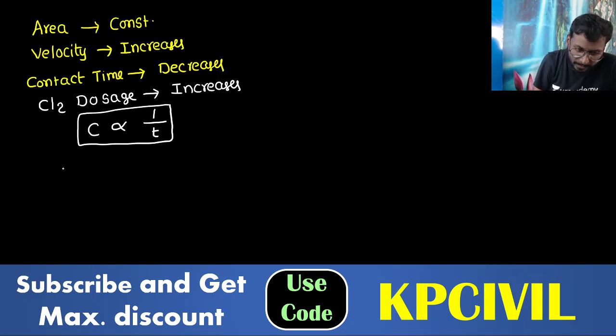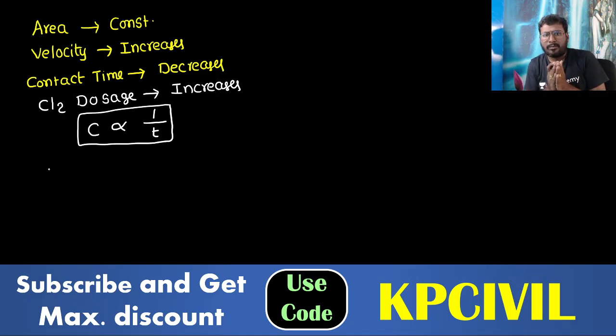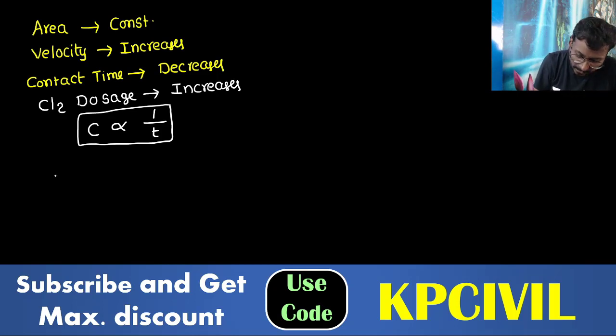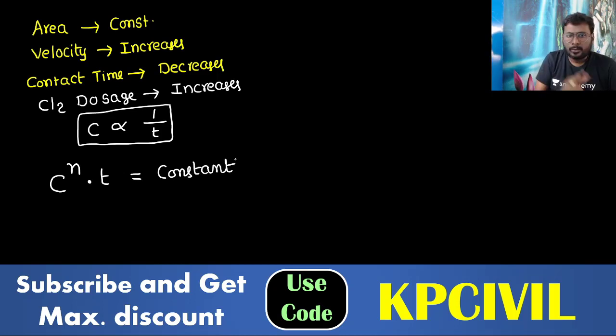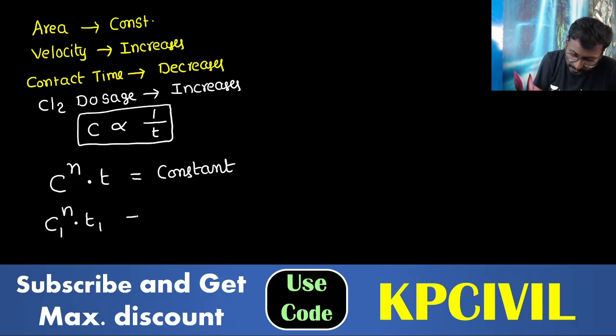So we'll take the formula. What is the name of the formula? Watson's law. Taking Watson's law, what do we take? C to the power n into T is equal to a constant. Two conditions are there here: the condition for 10 MLD and the condition for 13 MLD. So what I am writing: C1 to the power n into T1 is equal to C2 to the power n into T2.